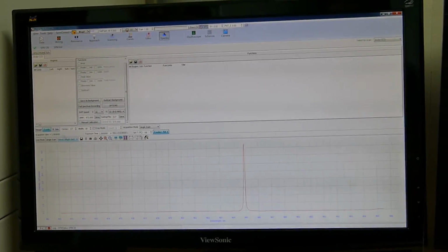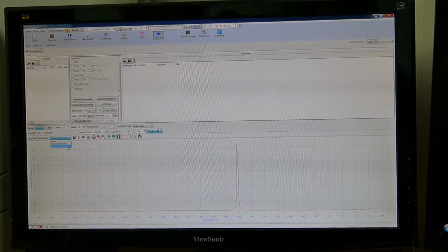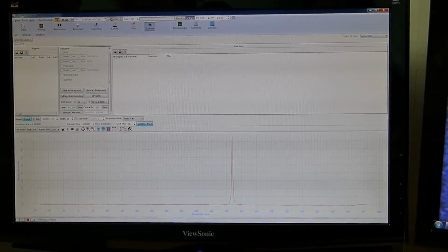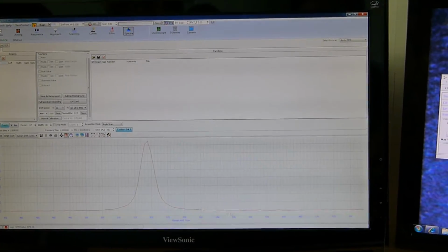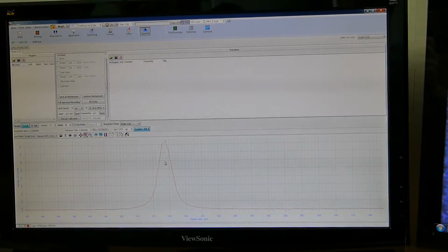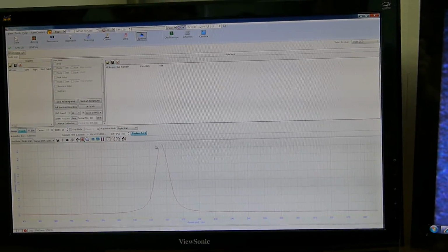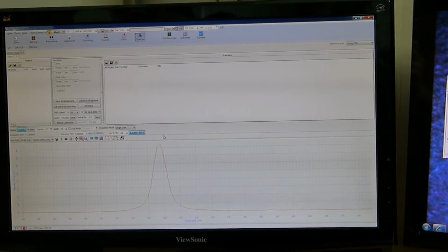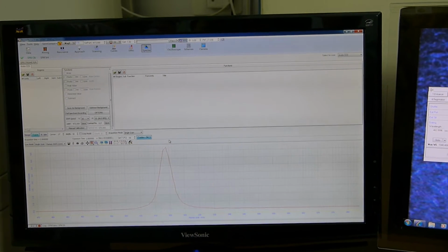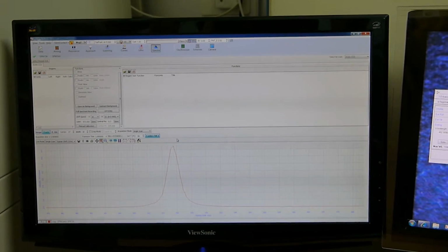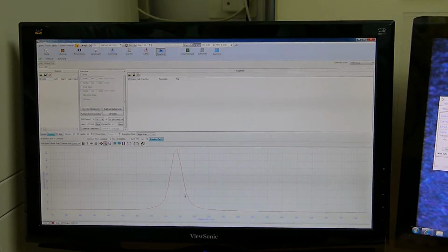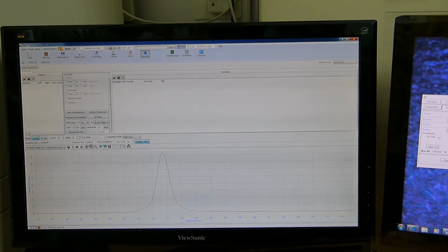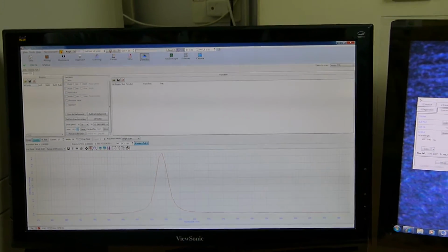If you switch to the Raman shift scale, it will show the Raman shift, and we can magnify this. About small shift, this grating has a resolution of 0.9 cm⁻¹. It can be plus or minus a little, 1 pixel. If you still feel that it's shifted, you can adjust a little somewhere here.